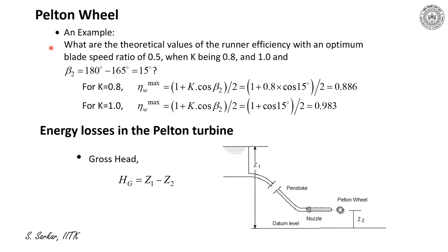Through an example, I have illustrated the variation of theoretical values of runner efficiency with an optimum blade speed ratio of 0.5 when k is 0.8 and 1.0 and beta 2 is 15 degrees. Here I have illustrated that for k equal to 0.8, eta w max would be 0.886, and again for k equal to 1, eta w max would become 0.983.